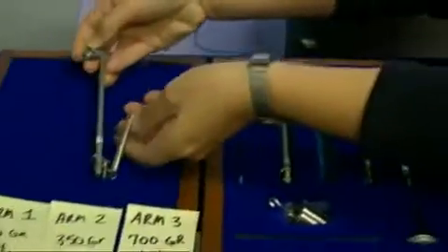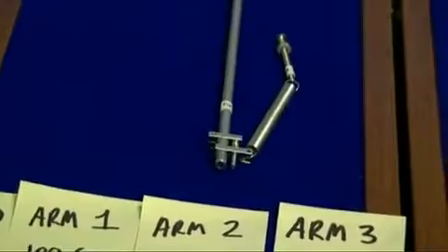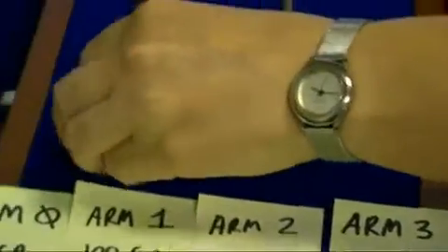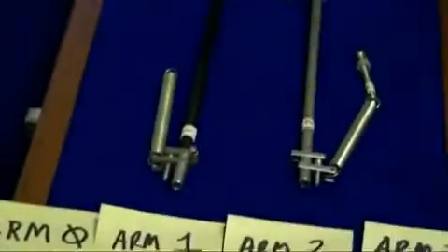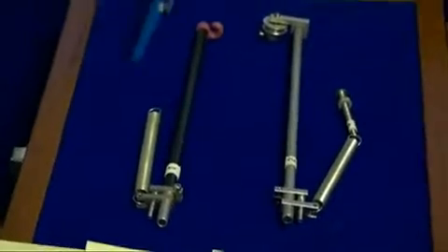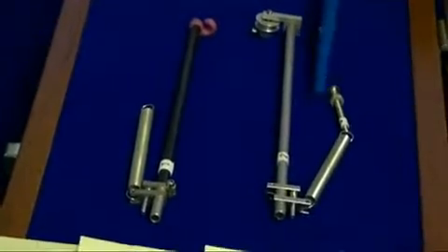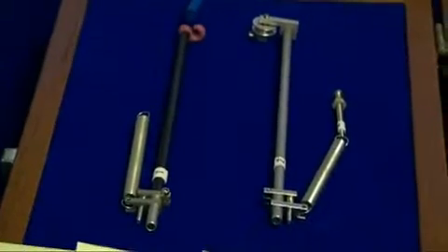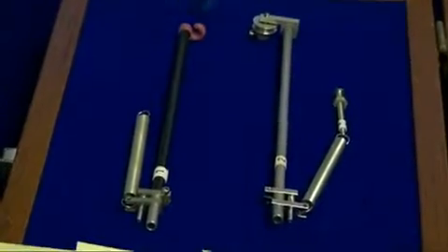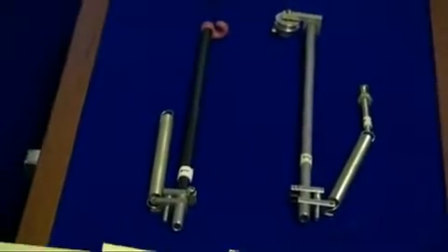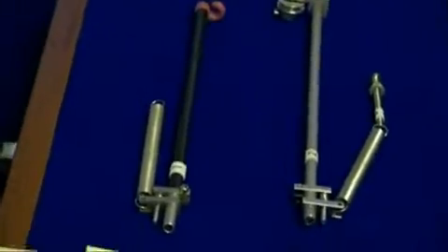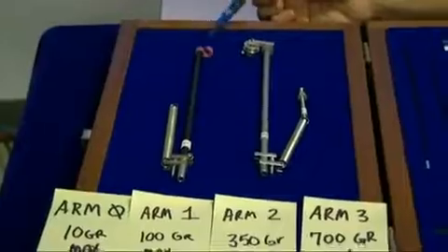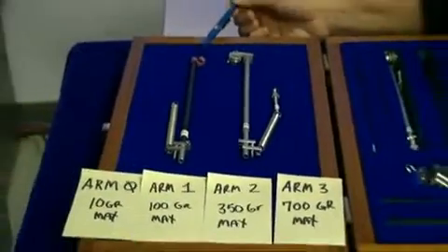When you start training your colleagues for the first time, you should be picking up arm number 2. Arm number 2 is one of the arms that has a strong spring. The main arm for the machine is arm number 1. However, as you can see, arm number 1 does not have a nut and screw assembly as shown on the other arms. The reason for this is arm number 1 is the main arm for the CTT machine, which means it is responsible for the calibration of all the arms plus the input tension levels on the machine.